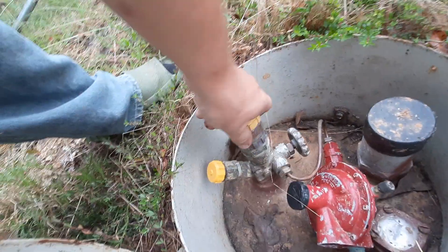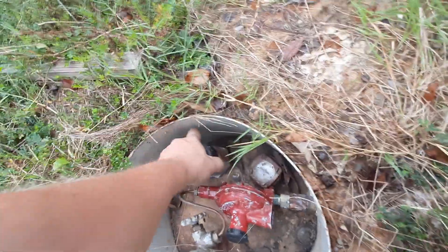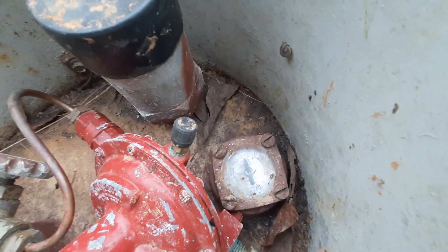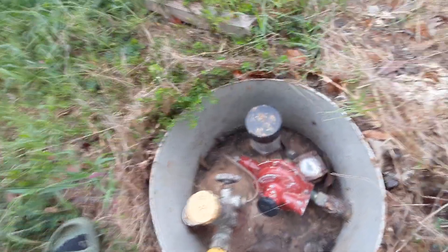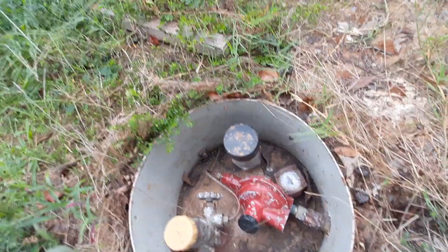There's that piggyback I was talking about — if you have one that's leaking, you put that piggyback on there and it'll take care of it. Right now you can see that tank — it's about 80 degrees outside and has 120 pounds of pressure. There's my blow-off and there's my gauge. That's the one with the four bolts — you have to replace the gasket on that type; you can't really just tighten them up.